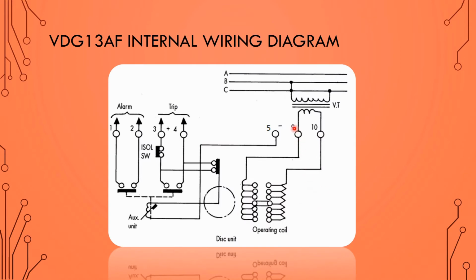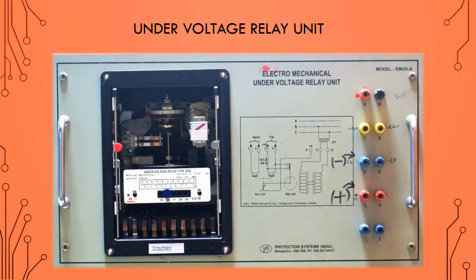This is the internal diagram, and this 9 and 10 are the input terminals of the relay unit, and 3, 4 are the trip signal or trip terminals of the relay unit. 1, 2 are the alarm terminals of the relay unit, and we can replace the trip terminal with the alarm terminal as a trip. So this is the under voltage relay unit. This relay is mounted inside the relay unit. As you can see, this relay is inside the black box, and the black box is inside the relay unit, that means inside the panel. And what is there inside the panel? All the terminal connections come out to this, this terminal, this 9 and 10, nothing but this 9 and 10 of the relay, and 7 and 8, 7 and 8, like that.